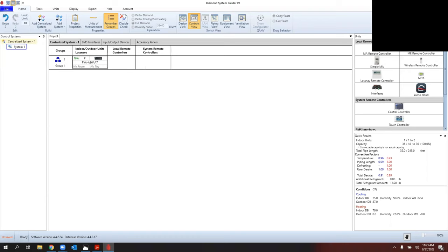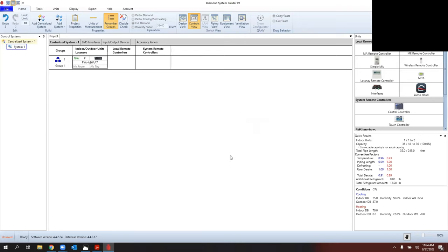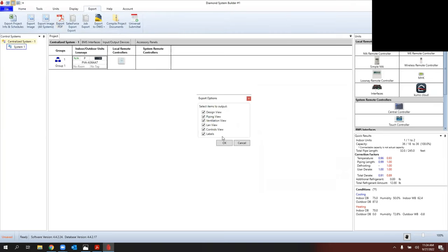Go back to home and click on Controls View. You'll see there's no controller selected. On a wall mount M Series system, it would auto-fill the included remote. On the right-hand side, I can select MHK — it gives you a checkbox, and if you have more than one unit, each gets Group 1, Group 2, Group 3. I'll select the most recent MHK2. When I hit OK, a picture of the MHK2 pops up, and now when I go to Export there are no errors.